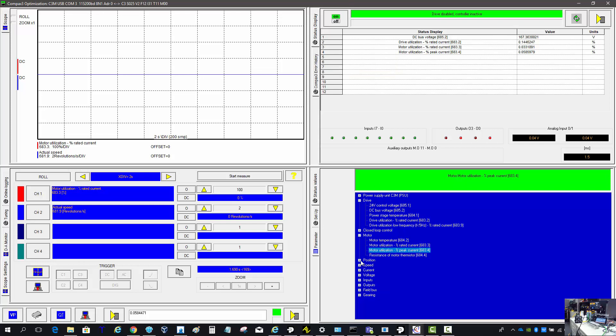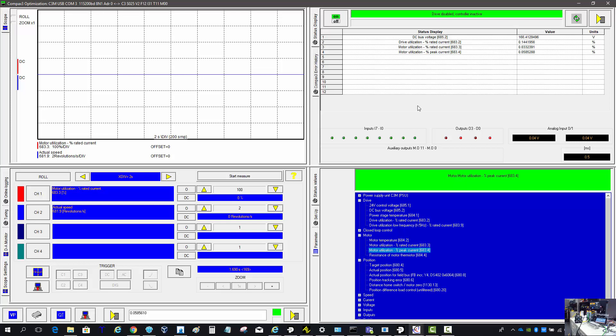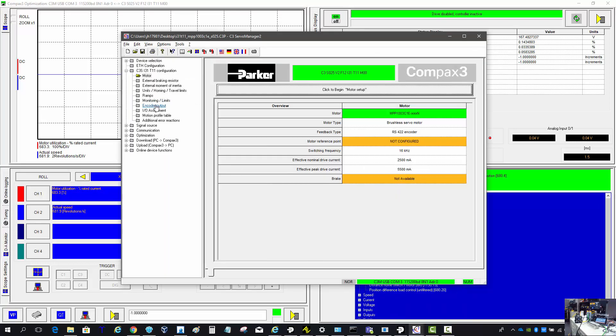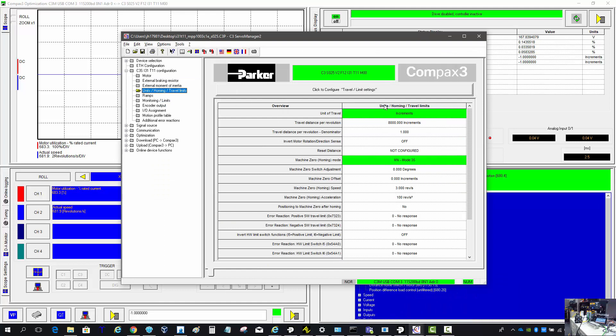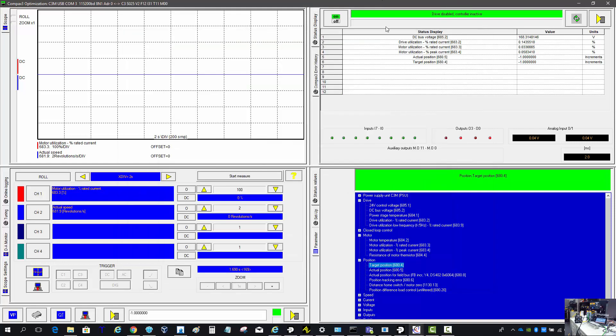Moving forward, another item I like to look at is the position — the actual position and the target position. Your units will probably be different than mine. The EtherCAT units are all done in increments, so I've got 8,000 counts per rev. Back in the main screen under your configuration, your units will be set there — it could be inches, millimeters, degrees, or increments. The position will be based on those units and that setting in the drive configuration.